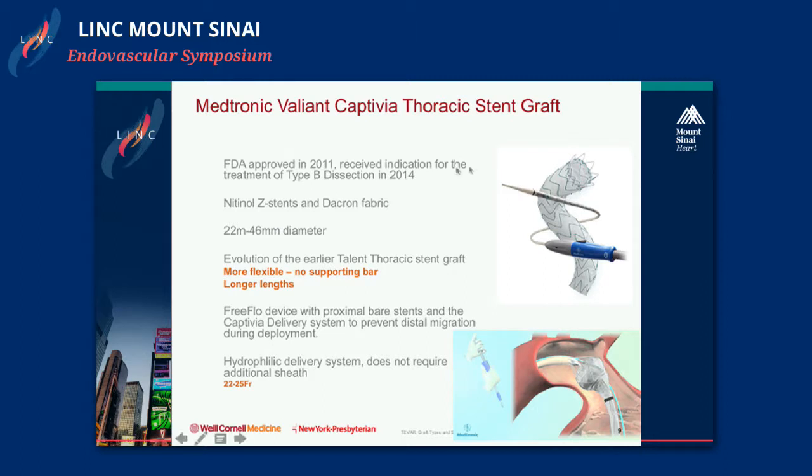The proximal extent of the Valiant Captivia is a FreeFlo design with a bare stent, while the distal end is flush. The delivery system has a constraining mechanism so the top stents are constrained until the device is ready for complete deployment, assisting with alignment and preventing distal migration. It features a hydrophilic delivery system that does not require an extra sheath, with an OD ranging from 22 to 25 French.